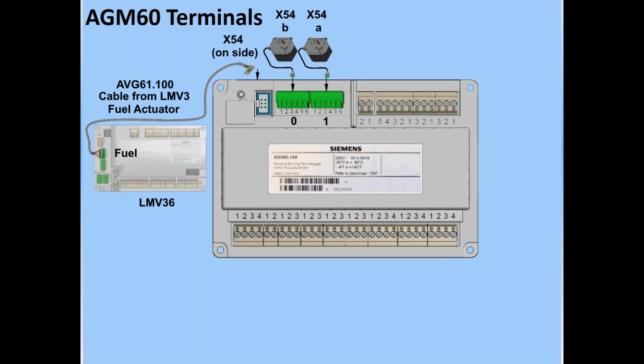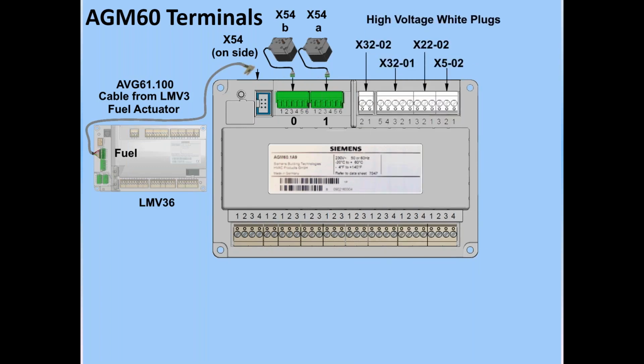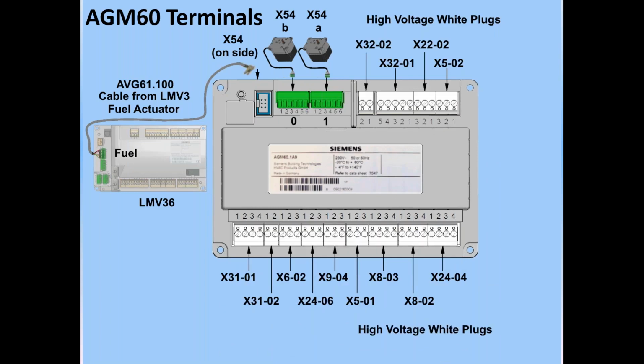The purpose of the AGM is to do fuel change, to take the single fuel chassis LMV3 and direct it to field equipment that goes to 2 different fuels. Additionally, we have white plugs on there. These would be controlling the outputs to the individual fuel valves for fuel 0 and fuel 1, and the inputs, such as high and low pressure switches and proof of closures for fuel 0 and fuel 1. Again, the AGM60 takes all of the 2 different fuels, the field equipment, and diverts them to the LMV3, depending on which fuel is active at the moment.